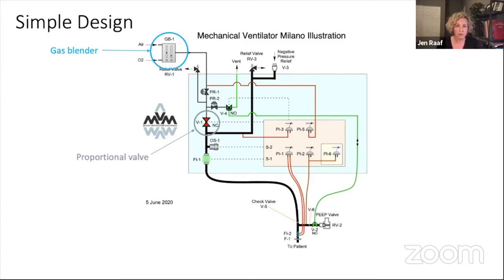This valve I've circled next controls the pressure provided to the patient. It's electrically controlled and adjusts how much it's open as part of a process control loop based on pressures measured elsewhere in the system.